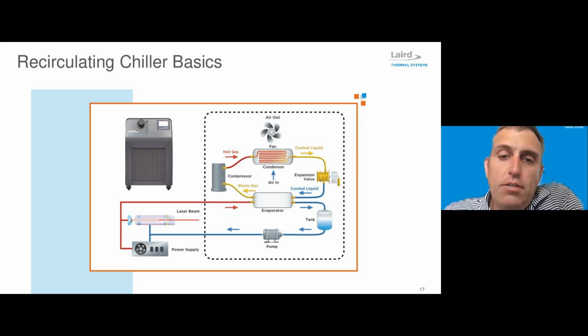On the refrigerant side, the evaporator is the means of exchanging heat between the coolant and the refrigerant. The compressor forces the refrigerant through another heat exchanger, which is called the condenser. And this is where the heat's rejected into the local environment. There are some systems that have liquid-cooled condensers, but I would say the majority of them out in the field are air-cooled.